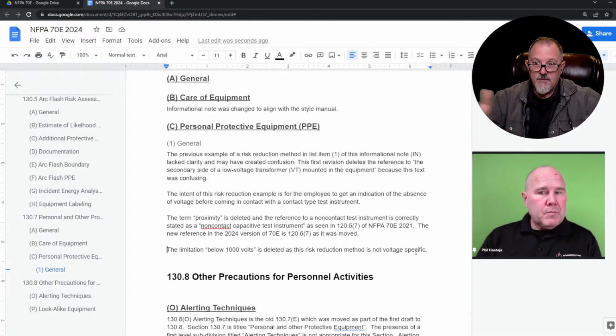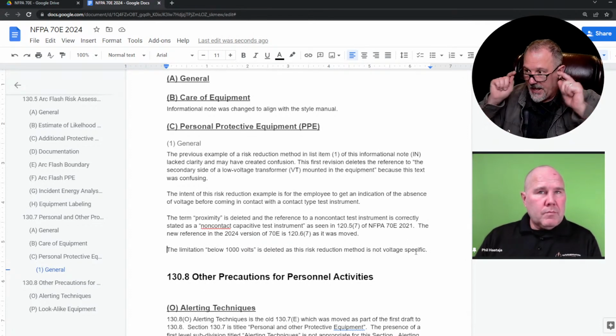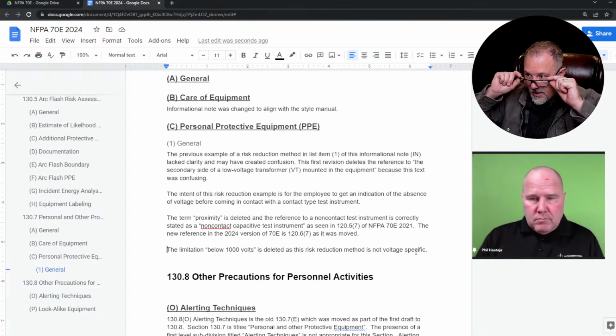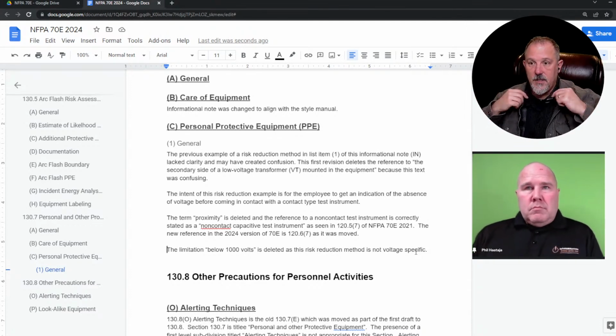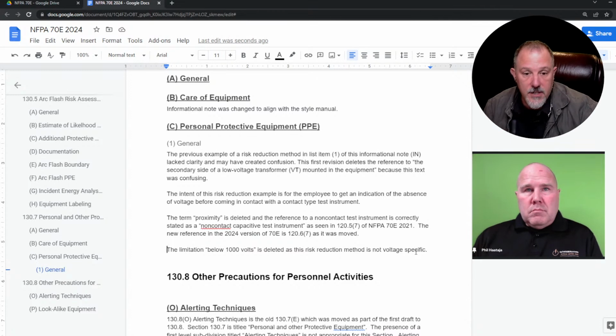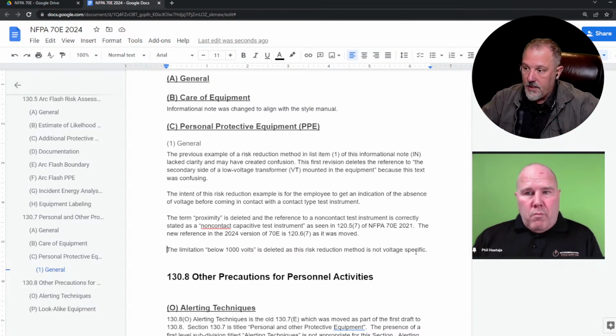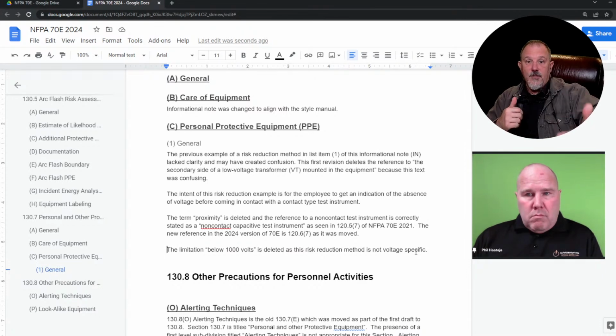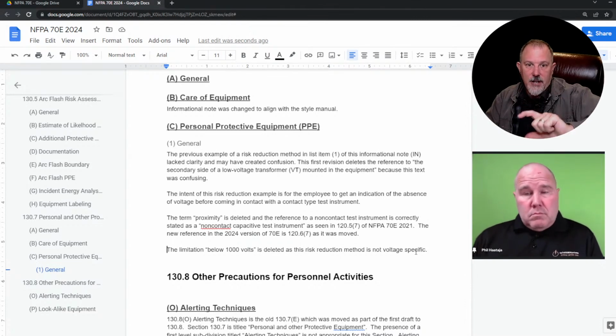So they have proximity testing, and I remember this discussion. They have non-contact capacitive test instruments for medium voltage applications too. This is an effective way to handle it, because remember, a good example is a medium voltage yard or service entrance equipment, where your incident energy is so high.